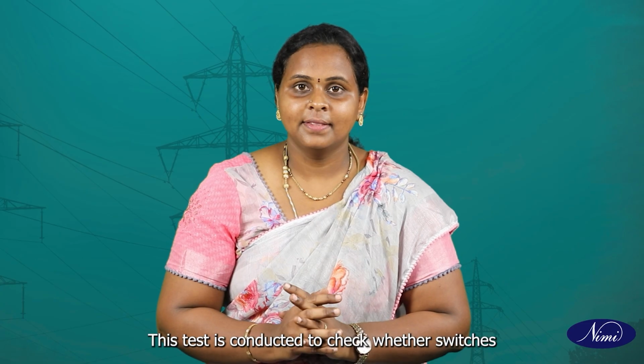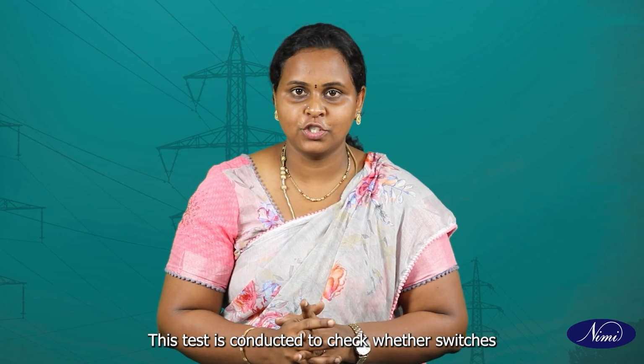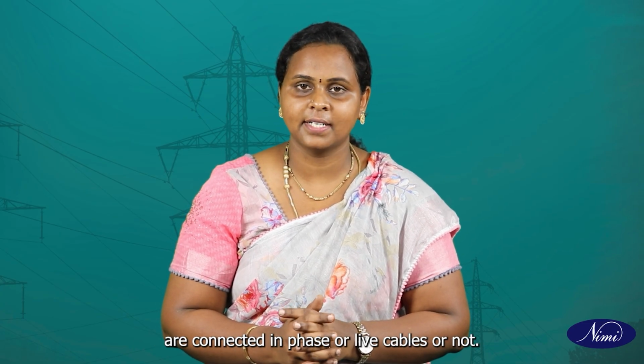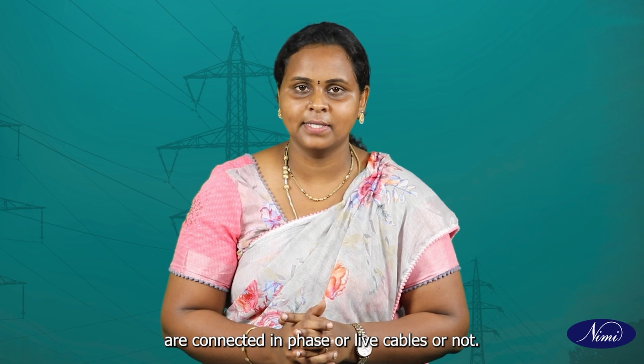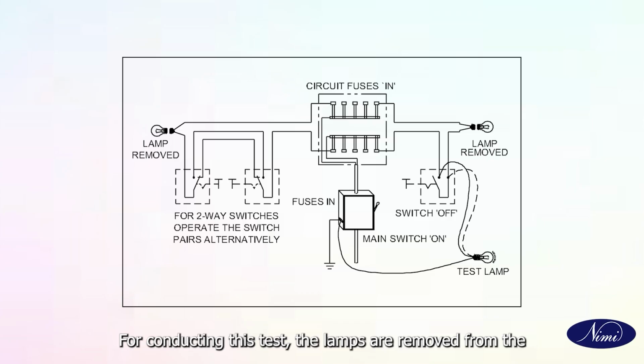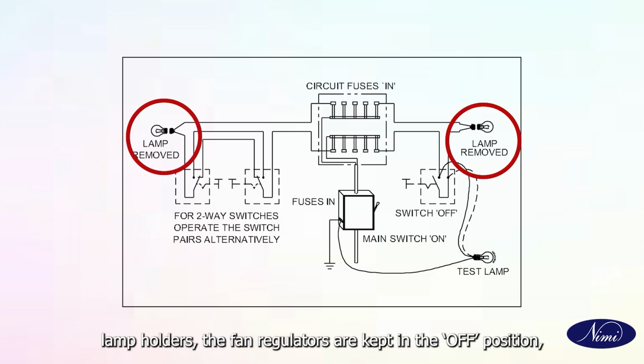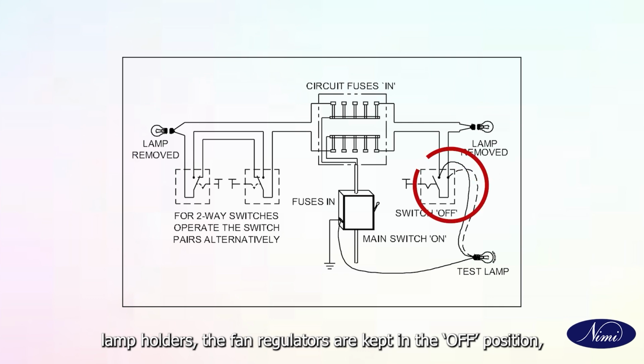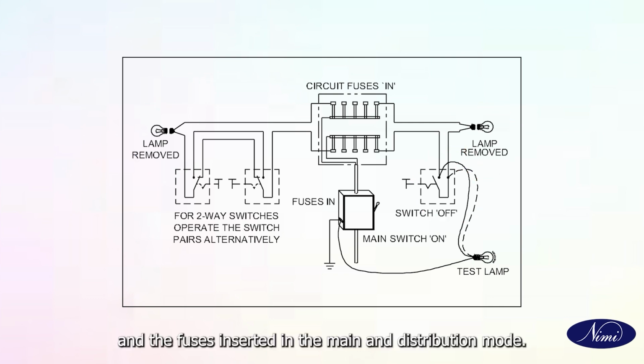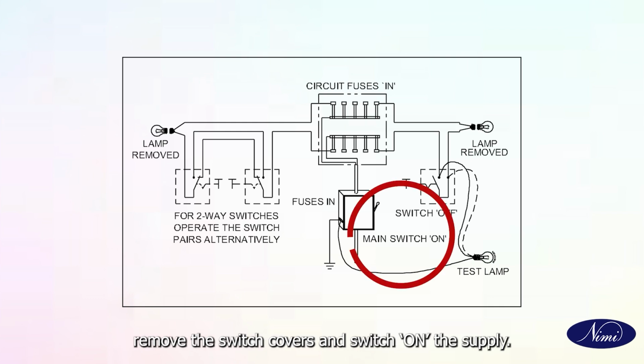Polarity test. This test is conducted to check whether switches are connected in the phase or live cables or not. For conducting this test, the lamps are removed from the lamp holders, the fan regulators are kept in the off position, and the fuses are inserted in the main and distribution board. Remove the switch covers and switch on the supply.